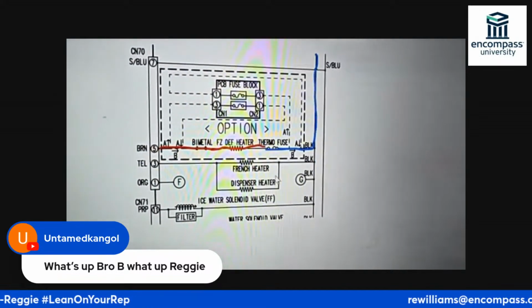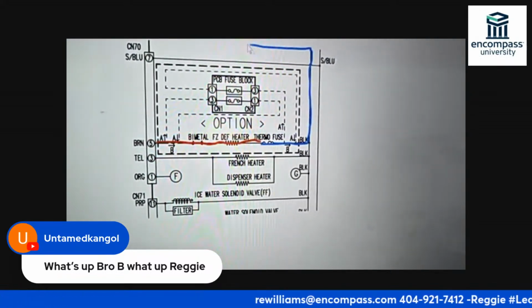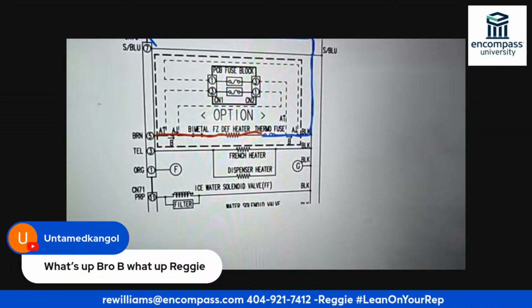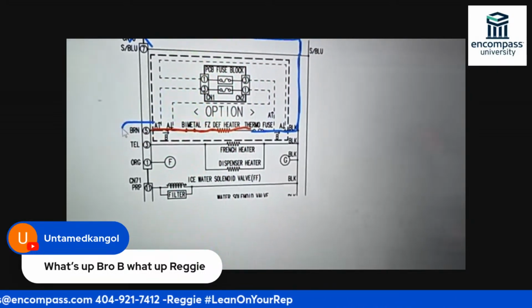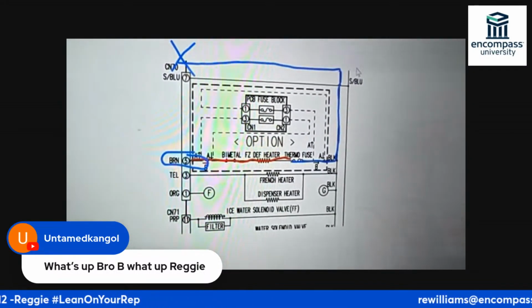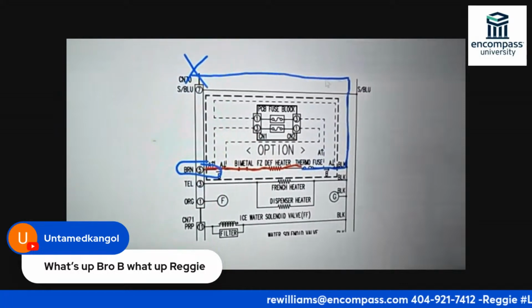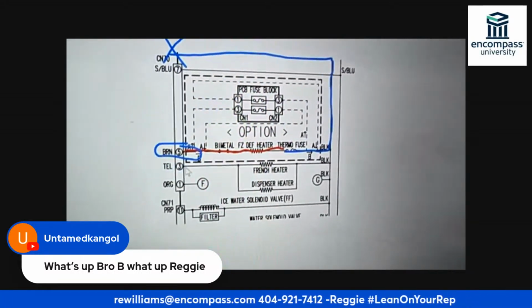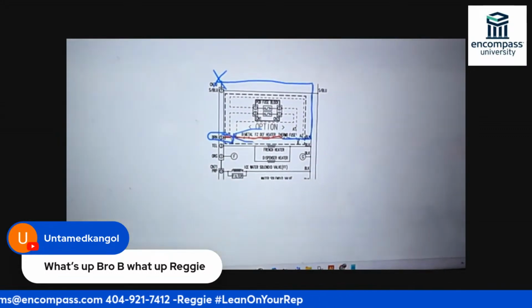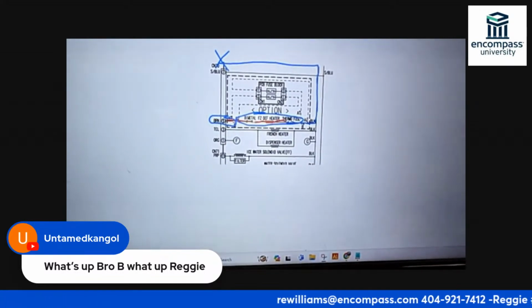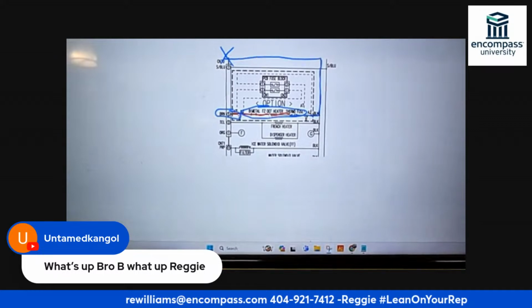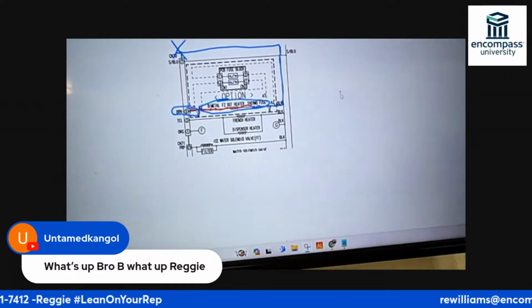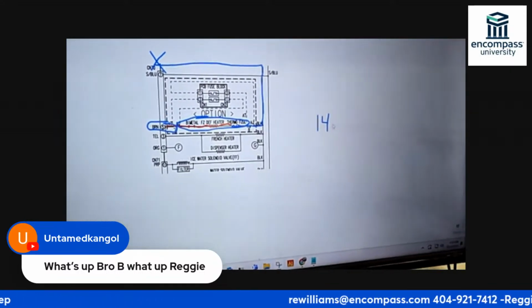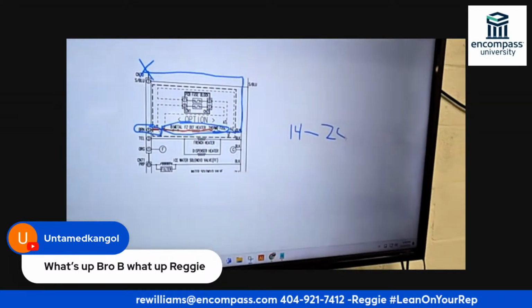And there goes my defrost circuit. I would come to the board, look for the neutral, measure here at the neutral spot and here at the output voltage, checking for 120 while the fridge is in a defrost cycle. Or I can unplug my leads and check for continuity across the entire circuit. If this fridge has a frozen evaporator, that bimetal should be closed, the defrost heater will give me a resistance, and if the thermal fuse is closed, I'll probably get something like 14 through 20 ohms.